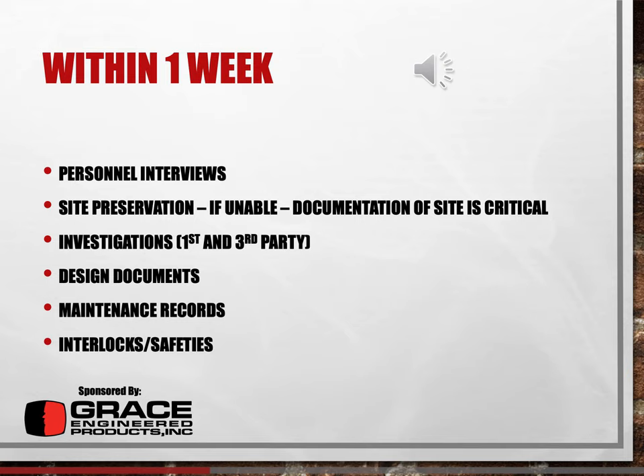You're going to want to start gathering design documents such as one-line diagrams and relay control diagrams, and any of those types of documents, physical layout diagrams. Next, you're going to want to start gathering maintenance records. Was the equipment maintained? Was it not maintained? When was the last time it was maintained? Were there any issues going on within the past 5 years or so that could have assisted in having this accident occur?